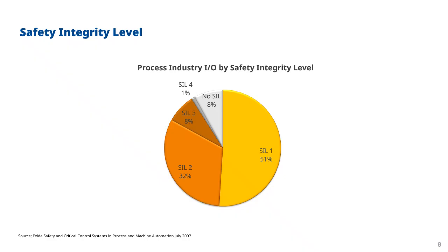For SIL 1 or SIL 2, normally you would use a similar level of control system, but the difference would be in the amount of testing and the amount of performance levels and the amount of additional calculations and the amount of additional mitigation factors you might need to perform. So I would often say SIL 2 and SIL 1 are very similar in terms of their requirements from the control point of view, but the documentation and procedures around it are a bit different, i.e. SIL 1 doesn't need as much work because, as we saw before, you're only looking at a 10 times risk reduction, whereas SIL 2 is 100 times risk reduction. When you get up to SIL 3, you've now got to perform a lot more mitigating factors. As I mentioned, we're now down at 1,000 times risk reduction, which means there's a correspondingly extra amount of work you need to do to make sure that that system does meet your SIL 3 requirements.